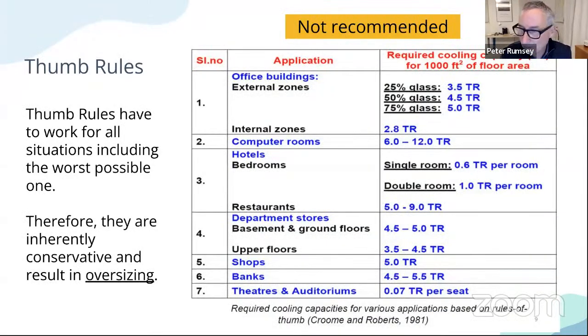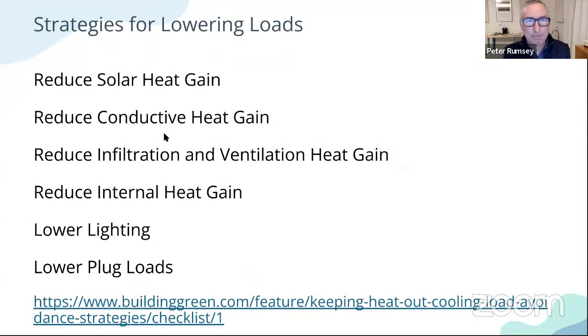I'd rather do a proper calculation. Many times I've done the proper calculation and compared it to the thumb rule, and our calculation comes up with a number that's half as big. When we do a calculation, we typically add a small safety factor, maybe 20%, but thumb rules often come up with 100% safety factor. It's way too much. So that's the whole thing about right sizing: do the calculation and you'll get exactly what you need.